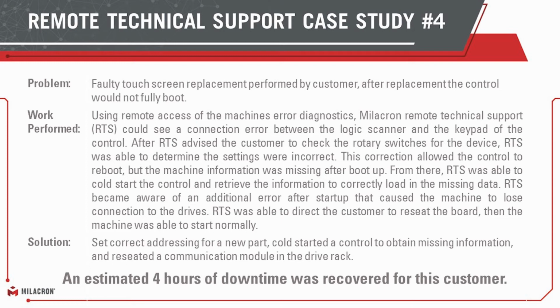This typically causes other problems, which relate back to the second error. When these connect, we actually have to address these items directly on the machine so it knows what to talk to. If it doesn't see it, the software doesn't match and it won't allow the control to boot. So very quickly we were able to say, okay, it's missing this certain piece of communication, it's likely something with the settings on the new component you replaced, and once you replace these dials, it will see it again and start working. And lo and behold, that ended up being the issue.